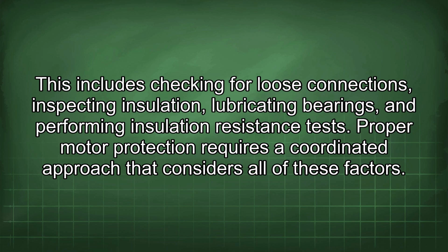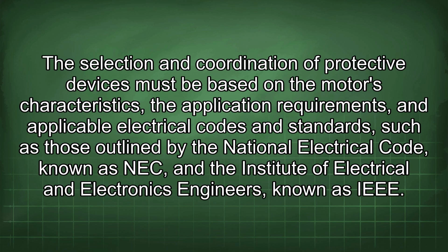Proper motor protection requires a coordinated approach that considers all of these factors. The selection and coordination of protective devices must be based on the motor's characteristics, the application requirements, and applicable electrical codes and standards, such as those outlined by the National Electrical Code, known as NEC, and the Institute of Electrical and Electronics Engineers, known as IEEE.